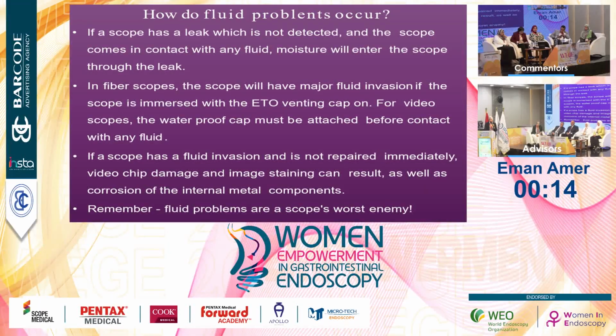How do fluid problems occur? If a scope has a leakage which is not detected and the scope comes in contact with any fluids, moisture will enter the scope through the leakage. The scope will have major fluid invasion if the scope is immersed in the ETO venting cap. For video scopes, the waterproof cap must be attached before contact with any fluids.